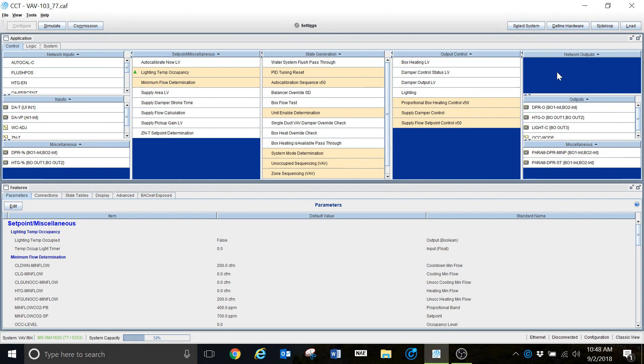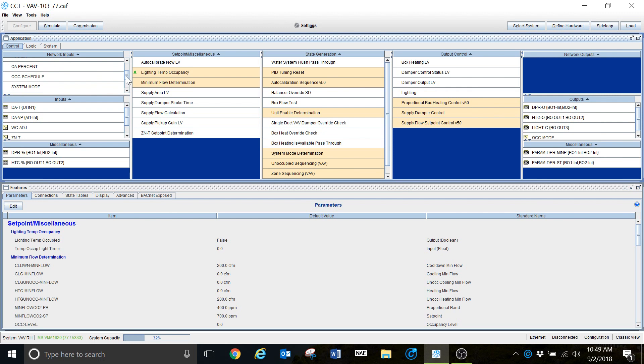In the upper section of this screen we have network inputs, hardware inputs, miscellaneous, set points, state controls, state generation, output control outputs, and miscellaneous again over here. The network inputs are points inside your system that may come from the Metasys system or Metasys server — hardware or software points that are going to be passed to the controller through the network. Things like zone temperature set point, tuning reset, heating enable — this is stuff you can see inside Metasys.